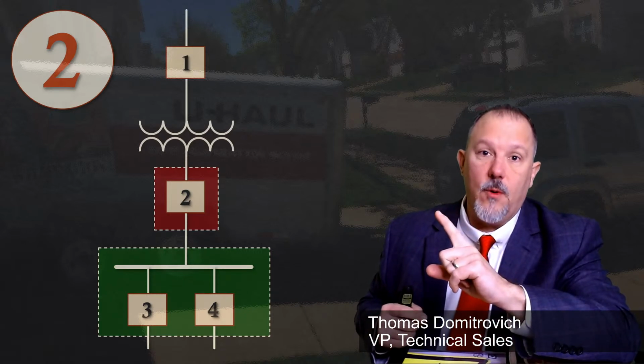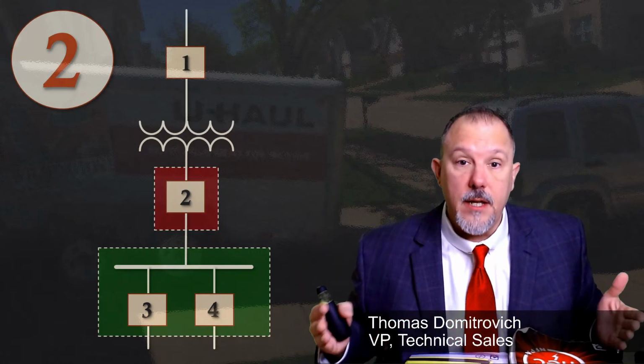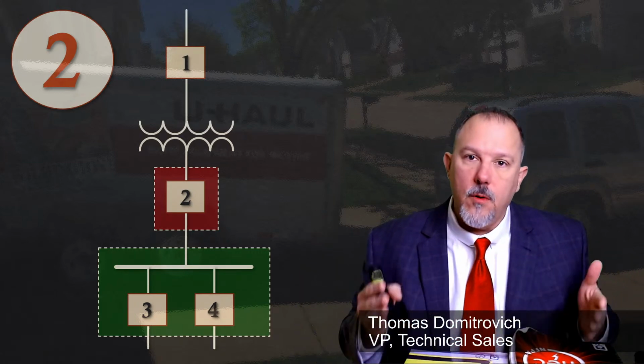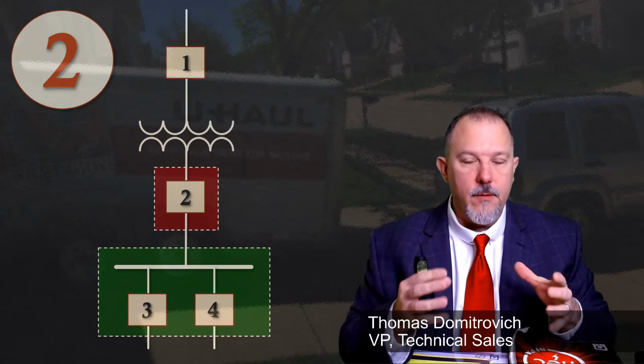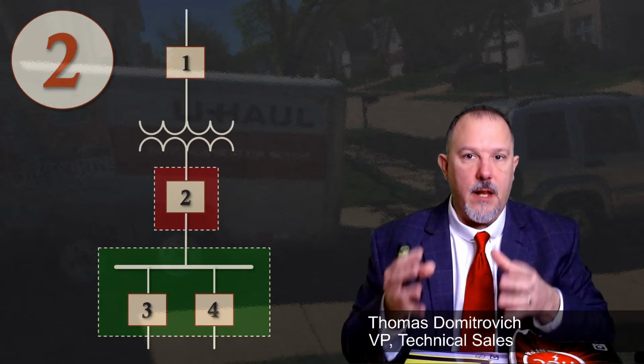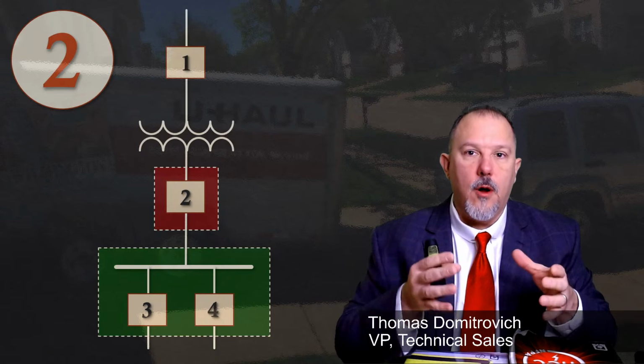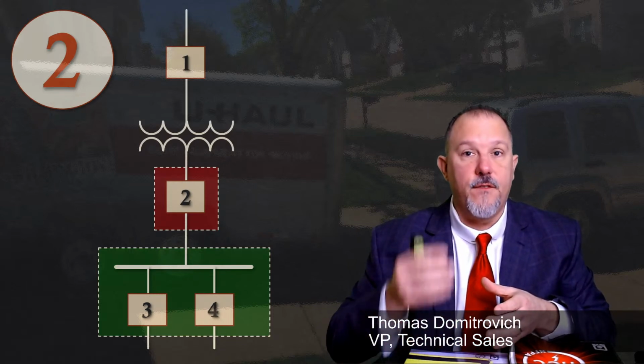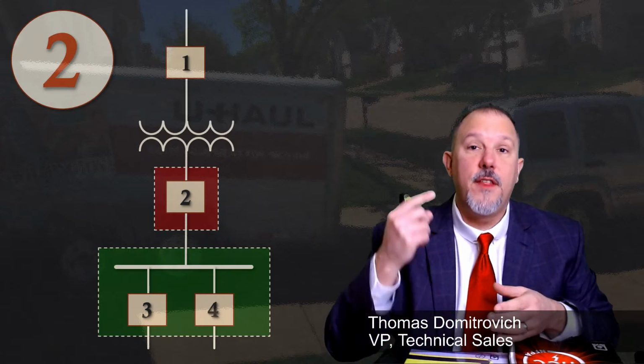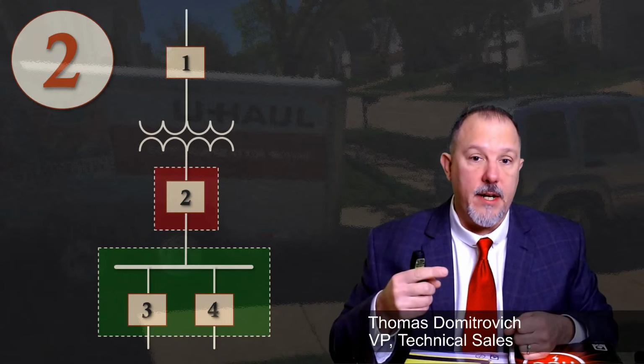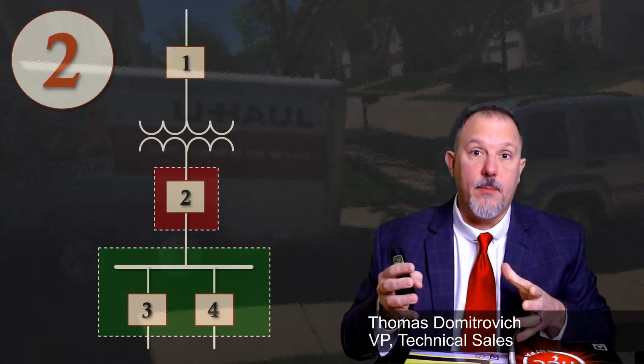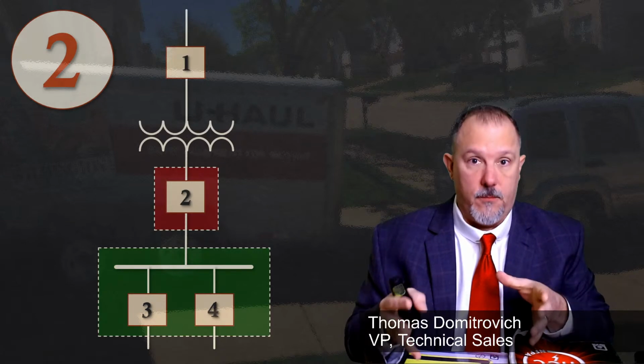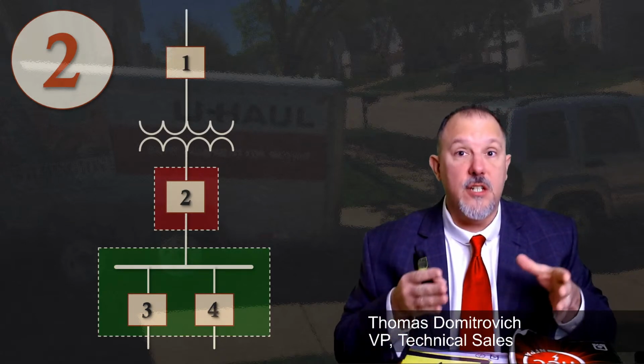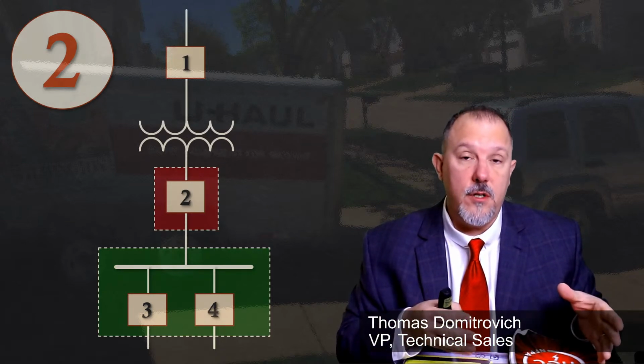And then that device number one is really who? The utility. But in this case, you're controlling the environment. Remember, it's about controlling the environment for the electrical worker. You are putting in place a method for them to establish an electrically safe working condition by putting this in a separate box as close to the equipment as possible, because availability is critical when it comes to safety solutions.